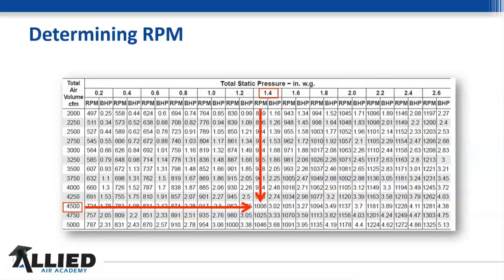And granted, I know some people have air balancing companies that come and do all this kind of stuff, but when you have to troubleshoot, or you have to go back and make sure they didn't mess up an adjustment or mess anything up, and so you got a low pressure switch going out because you're not moving enough air, this is going to help you as well too.